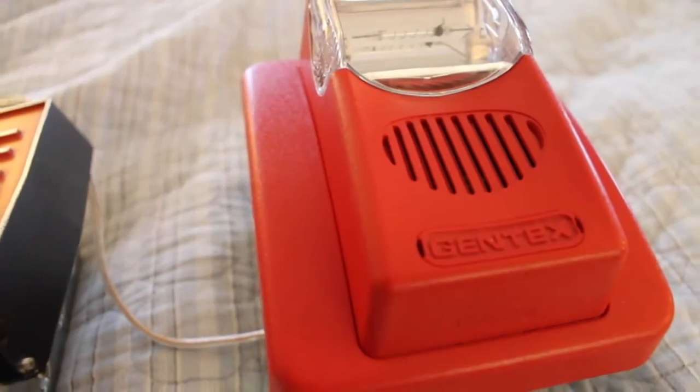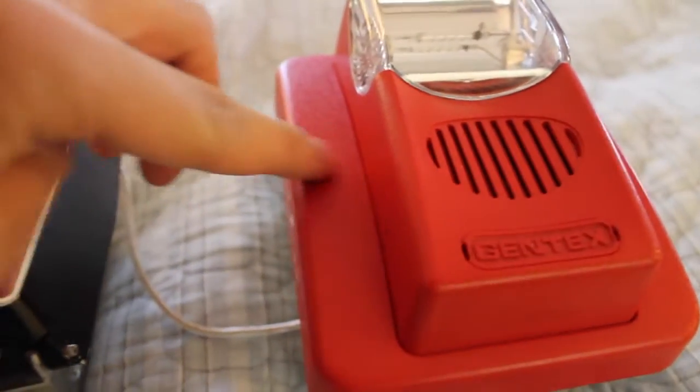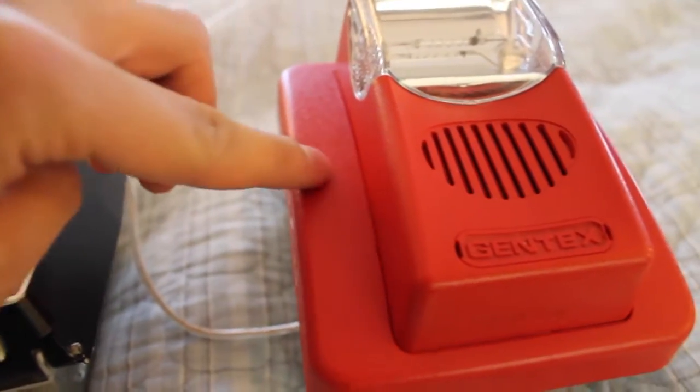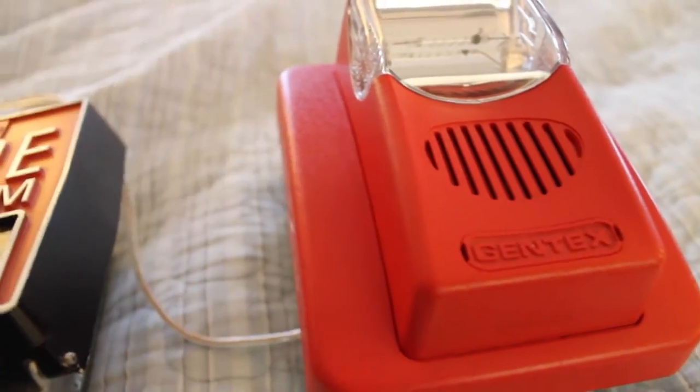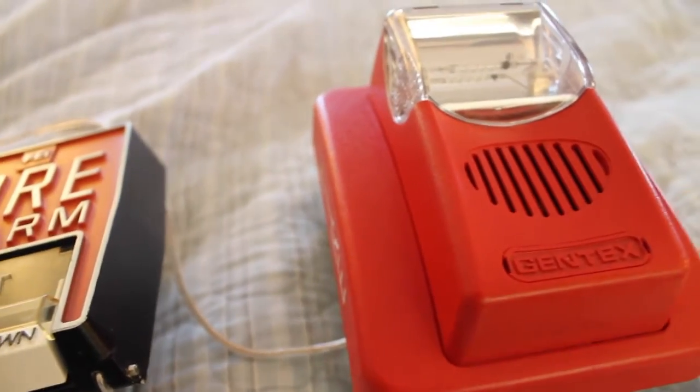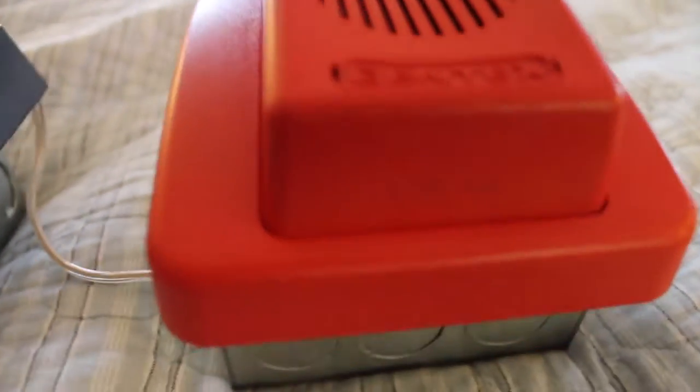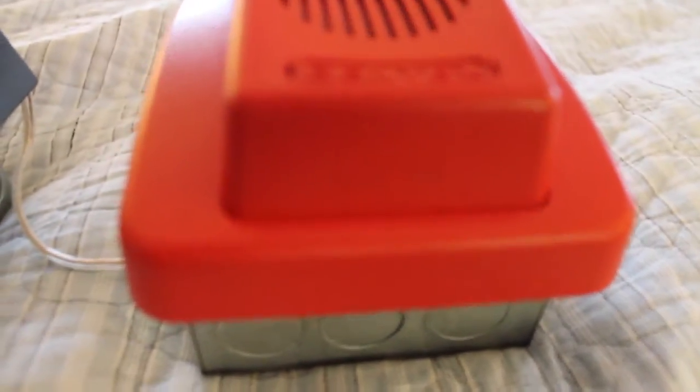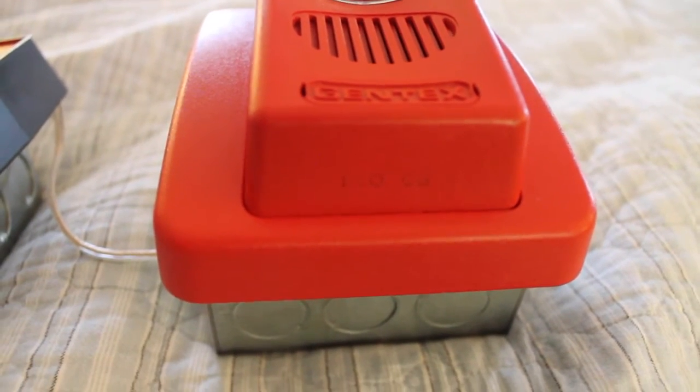Let me just focus right here. It would normally be right over here with a 15, 30, whatever. However, it's down here, the candela indication. This particular one is 110 candela.